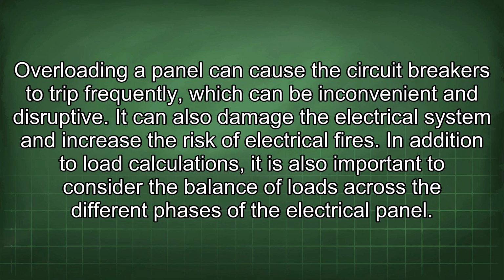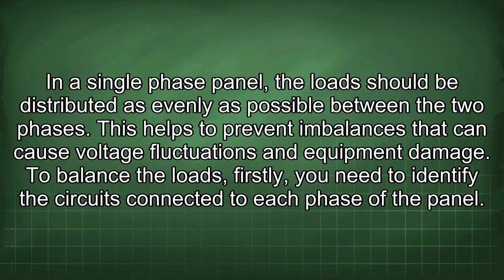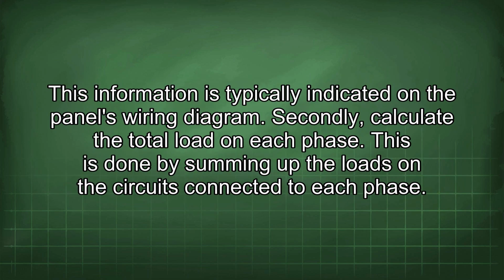In addition to load calculations, it is also important to consider the balance of loads across the different phases of the electrical panel. In a single-phase panel, the loads should be distributed as evenly as possible between the two phases. This helps to prevent imbalances that can cause voltage fluctuations and equipment damage. To balance the loads, firstly, you need to identify the circuits connected to each phase of the panel. This information is typically indicated on the panel's wiring diagram.